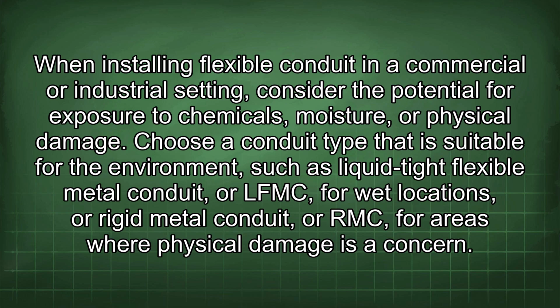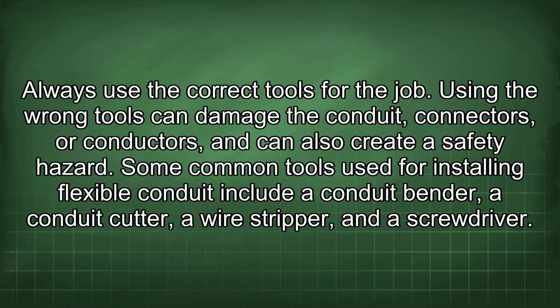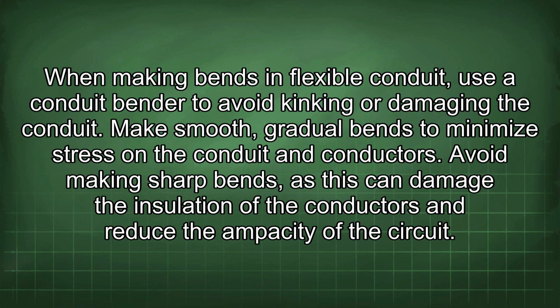When installing flexible conduit in a commercial or industrial setting, consider the potential for exposure to chemicals, moisture, or physical damage. Choose a conduit type that is suitable for the environment, such as liquid-tight flexible metal conduit, or LFMC, for wet locations, or rigid metal conduit, or RMC, for areas where physical damage is a concern. Always use the correct tools for the job. Using the wrong tools can damage the conduit, connectors, or conductors, and can also create a safety hazard. Some common tools used for installing flexible conduit include a conduit bender, a conduit cutter, a wire stripper, and a screwdriver. When making bends in flexible conduit, use a conduit bender to avoid kinking or damaging the conduit.